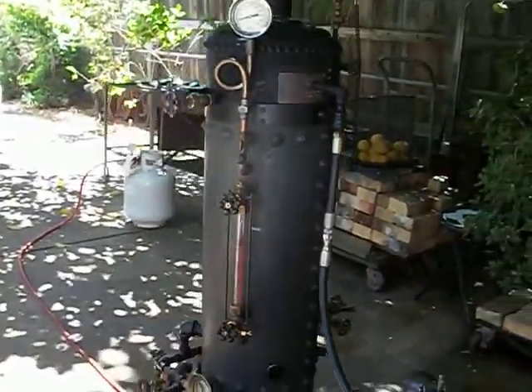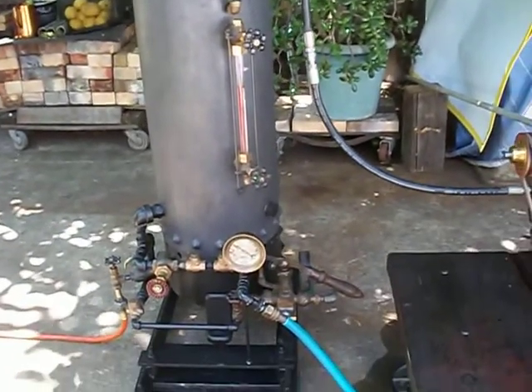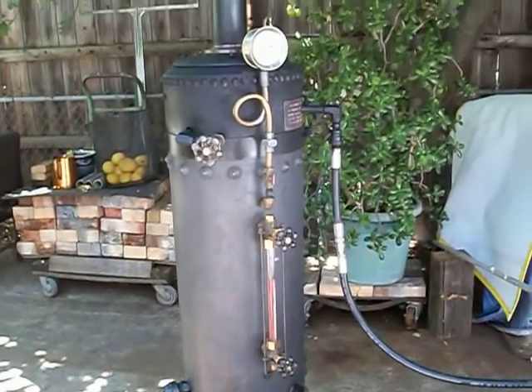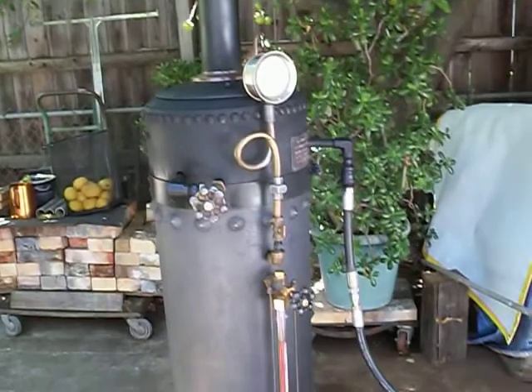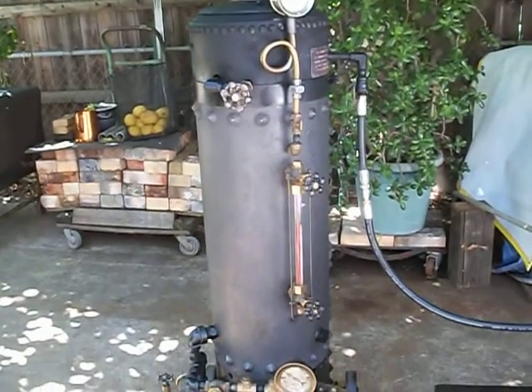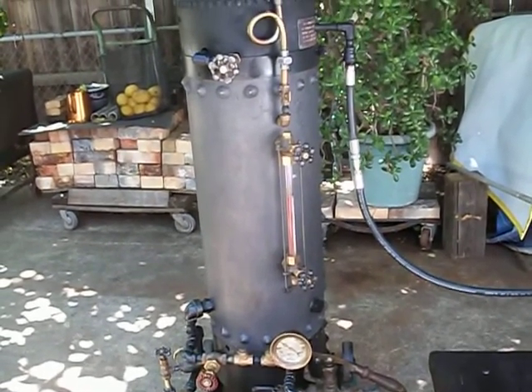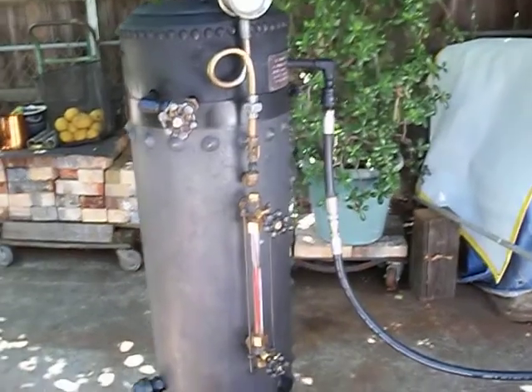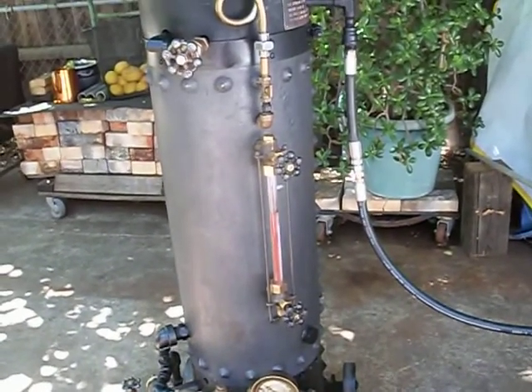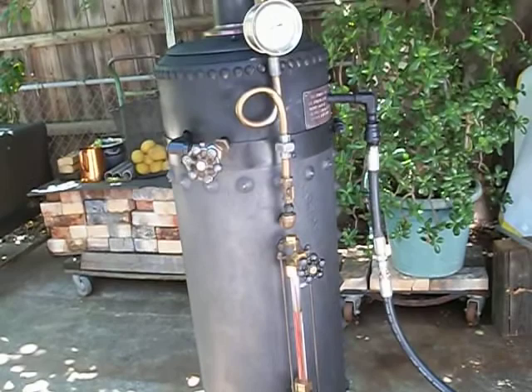We leave the engine and go over to its power source, which is an early Chinese laundry steam boiler, very graciously given to me by Larry Snow — thank you, Larry. We completely went through this boiler. An engineer friend of mine spent a lot of hours running calculations on the boiler shell, and with a set of ultrasonic readings, he calculated this boiler's working pressure.